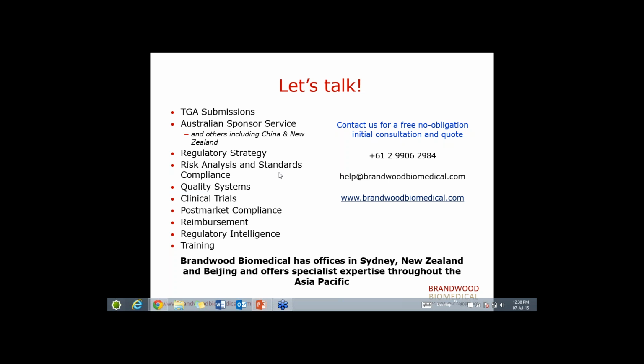Now, from the last slide, when I mentioned that the new law allowed local Australian manufacturers to basically use an EC certificate, the answer is you don't need both. You only need one now. The recommended strategy is to keep the EC certificate, only because we do find it's a lot easier to deal with the notified bodies, and it's easier to just have it under the one certificate.